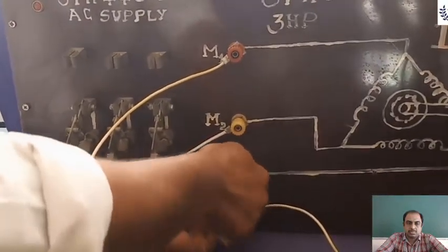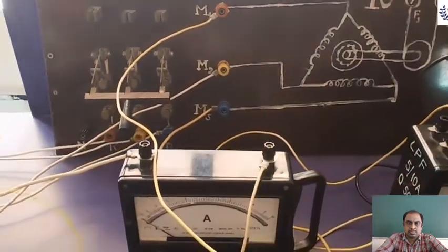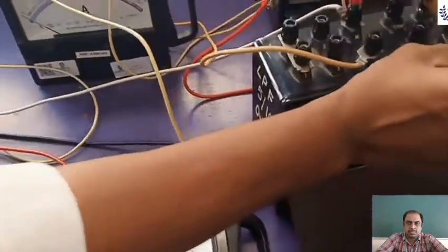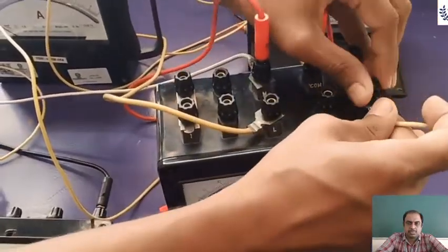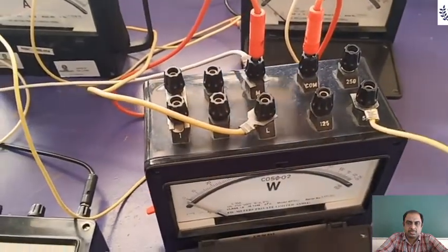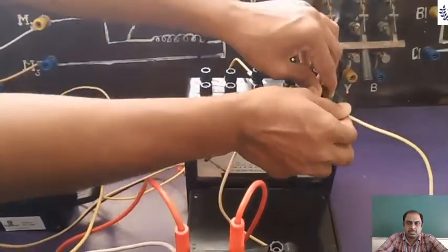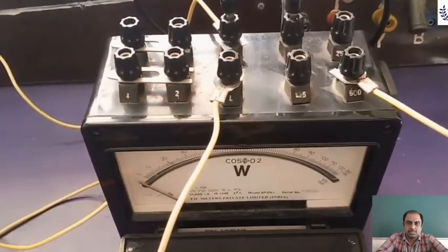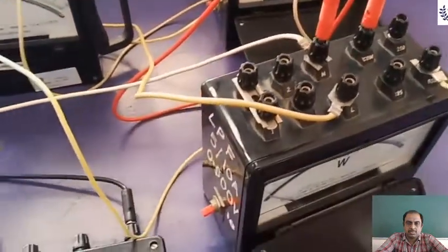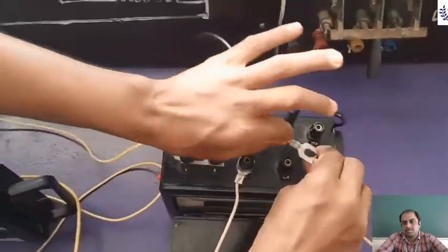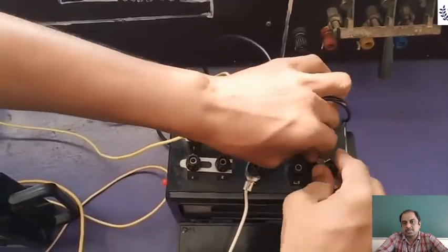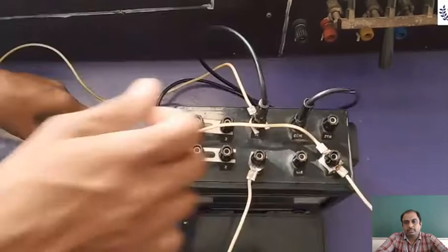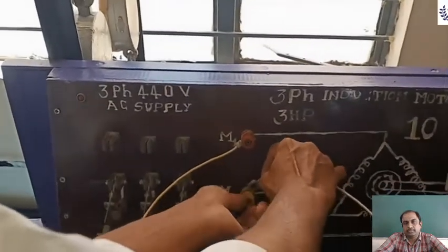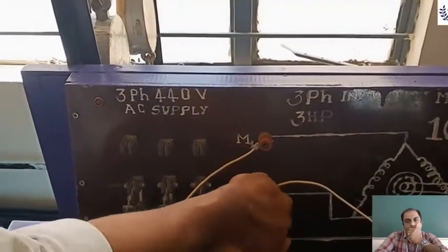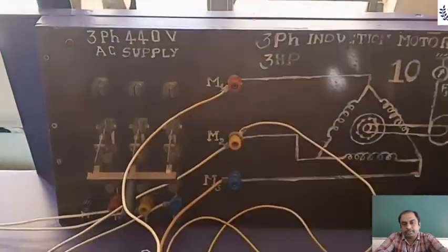M3. Then for the wattmeter 500 volt, we can connect it to wattmeter 1 500. Because here the input line is 415 volt and we are operating through the auto transformer, we can give a maximum of 500 in the wattmeter. So from wattmeter 1 500 to M2 of the stator winding.